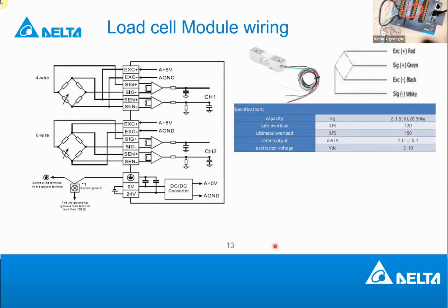So what I was saying before I was interrupted was that each sensor has what you call a specification. One of the specifications that is very, very critical is the gain value, the rated output. The rated output determines what the sensor measures. In this case, it is 1 millivolt for 5 kg. Each sensor has a different gain value that has been specified. So in the load cell wizard, if you are configuring this load cell for your application in the software, you need to select a gain value of 1 millivolt, and then you are done. Your settings will be correct.